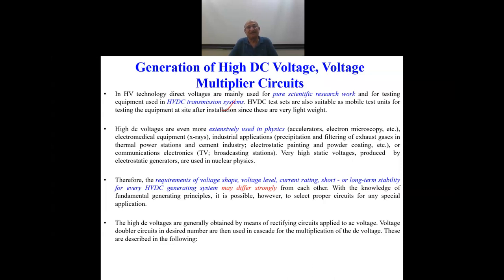Another use of high voltage DC test sets is for scientific research work. There are certain kinds of scientific research work which require high voltage DC. Then, as we were talking about the power frequency test set which can be taken to the site because of its low weight, the same thing is true when you want to test equipment at the site. So far it has been practiced, and is still practiced, that at site even AC equipment is tested with DC, because the mobile unit of DC is much lighter.